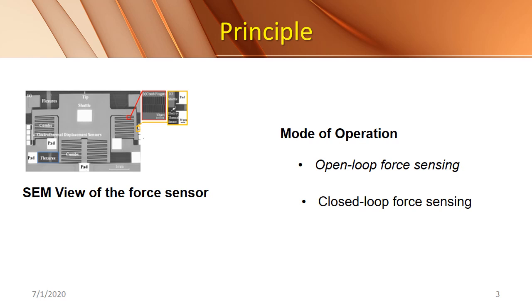The operation of this device is of two types: open loop and closed loop force sensing. In open loop force sensing, the displacement of the sensor probe is measured, and by knowing the stiffness of the probe, the applied force is determined. In closed loop, a controller is included to receive feedback, which could be nonlinearities arising from the mechanical flexure, and the controller would then compensate for them.